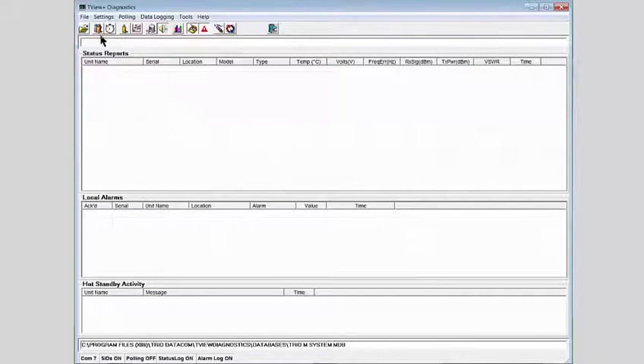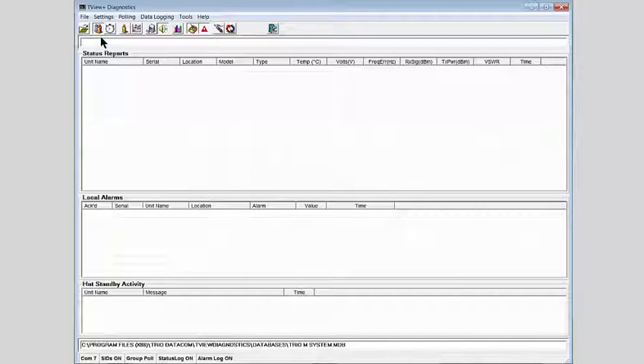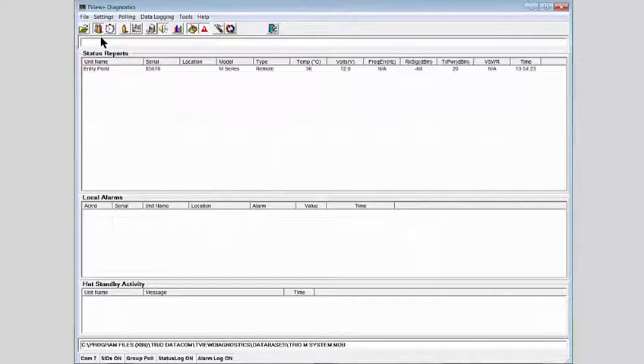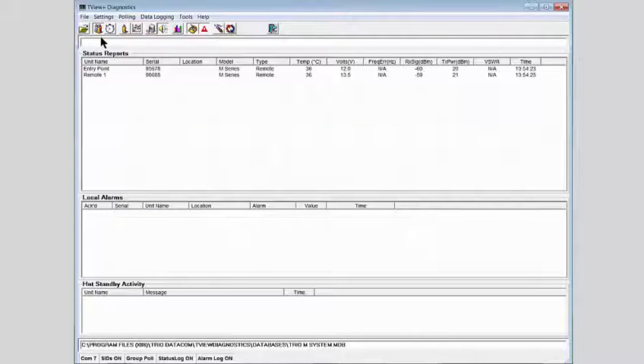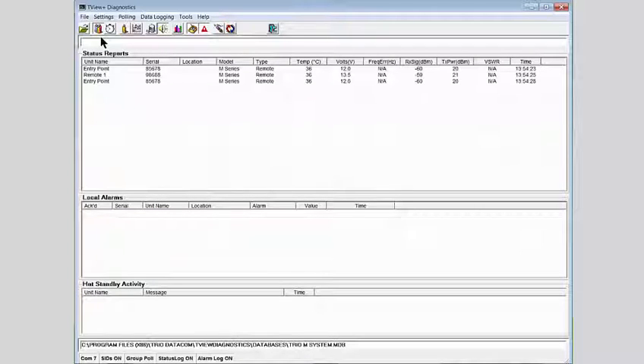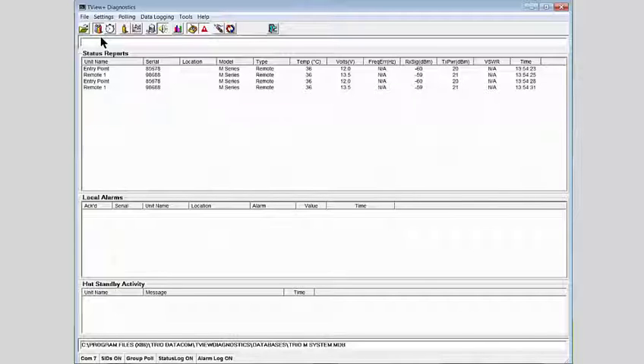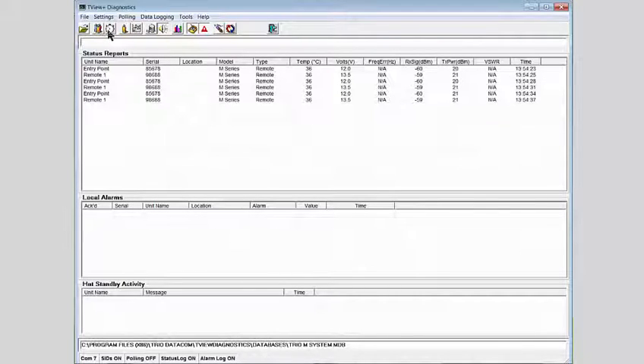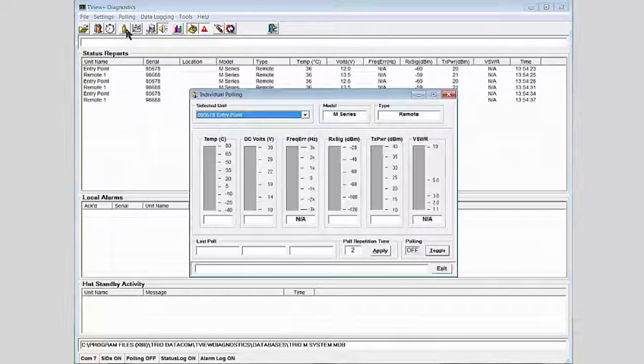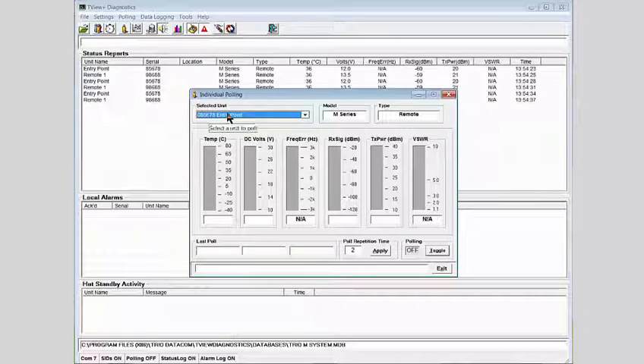Now, we can press the group poll button and this will poll each radio in turn. We can then note the received signal level of approximately minus 60 dBm as predicted, the transmit power, and other settings.